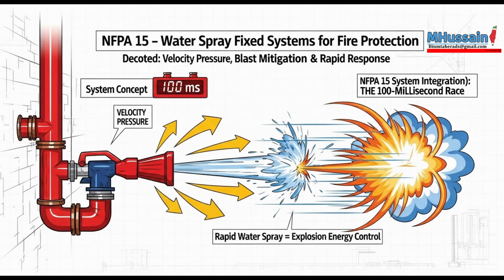You have to factor in burning liquid flow, hot gases setting off adjacent detectors, even the possibility of someone manually activating multiple systems from a control room. The engineer's job is to identify the single, credible, worst-case scenario based on fire dynamics and detection logic and design the water supply for that combined flow rate. Okay, we've set the goals, figured out the worst-case flow rates. Now we get to the absolute core of the engineering. Chapter 8. Plans and hydraulic calculations.